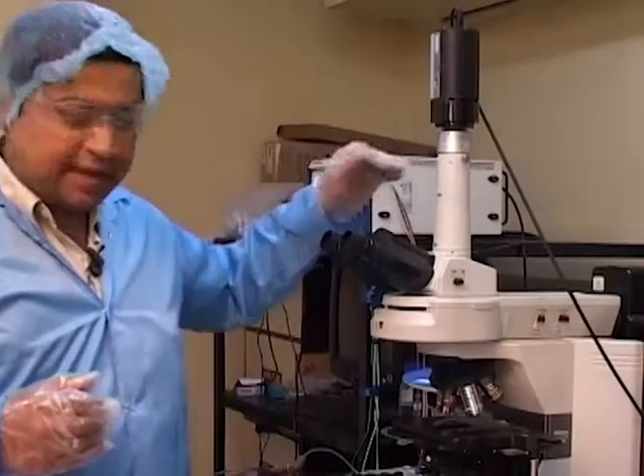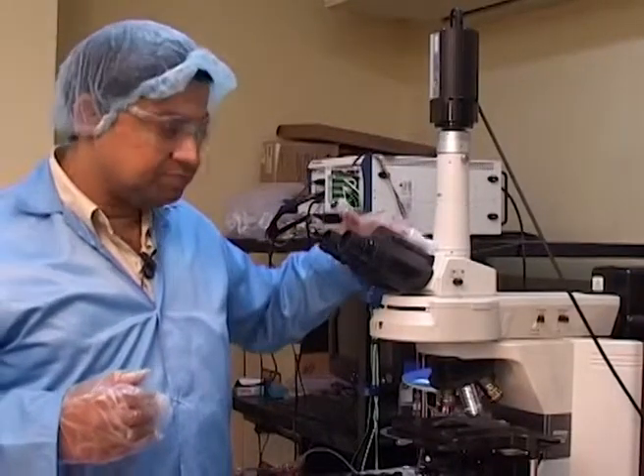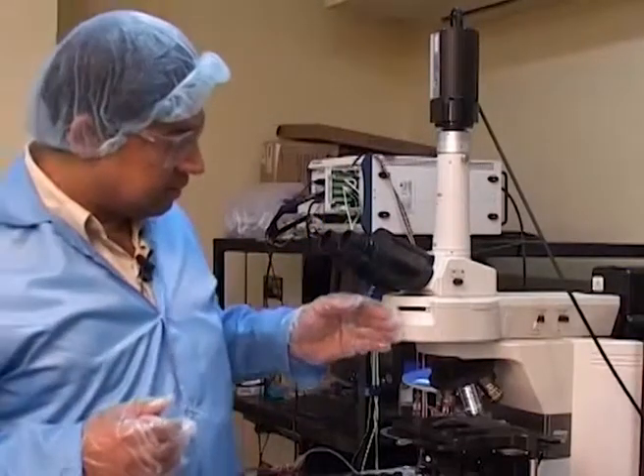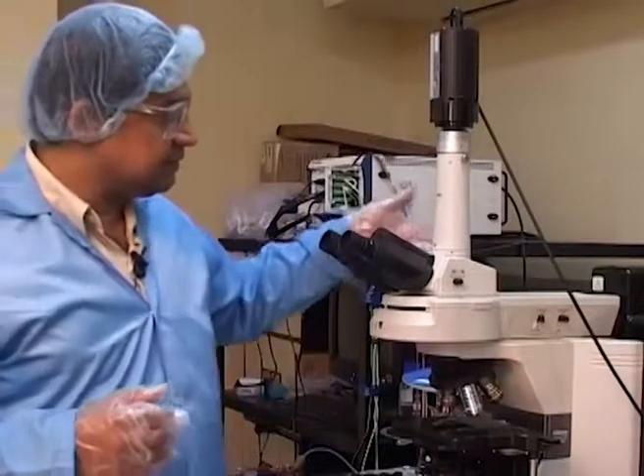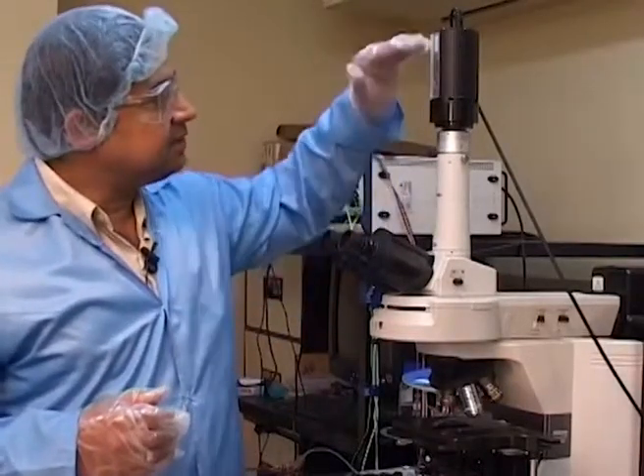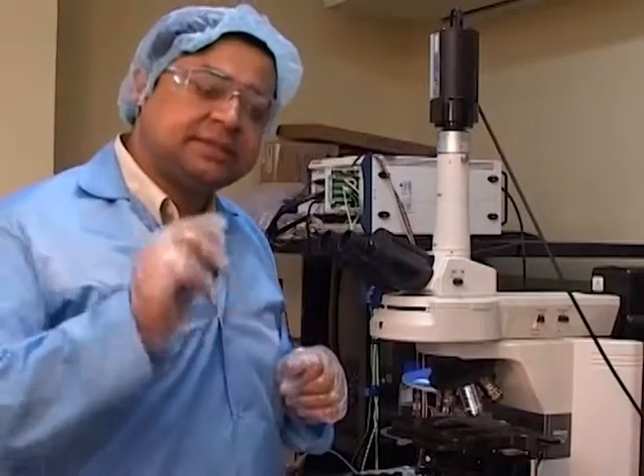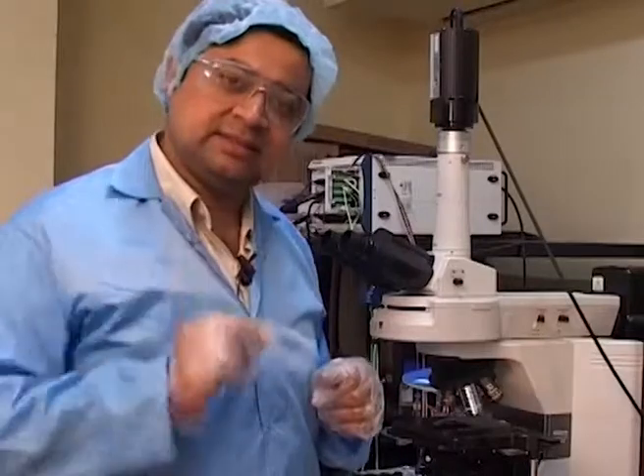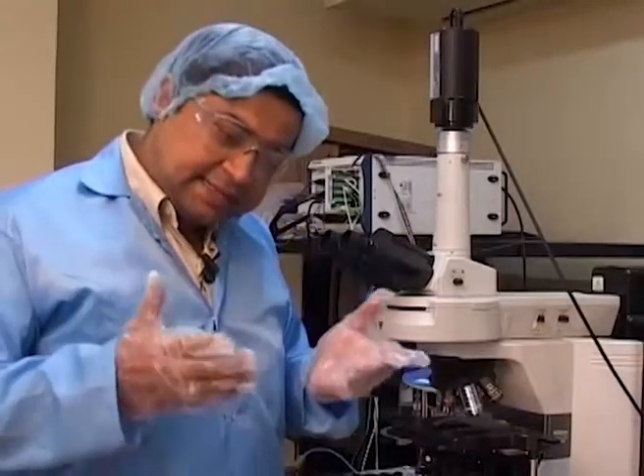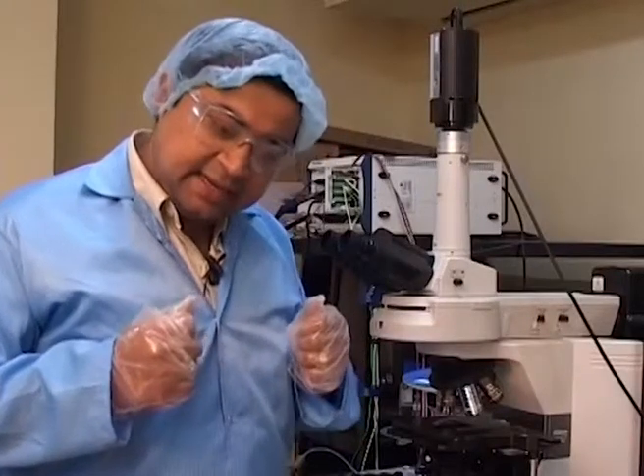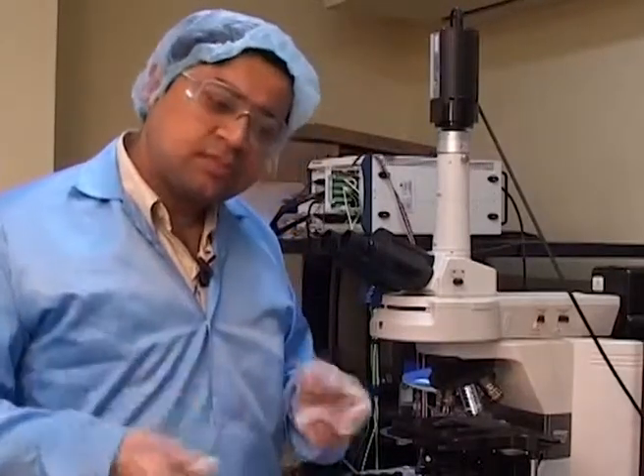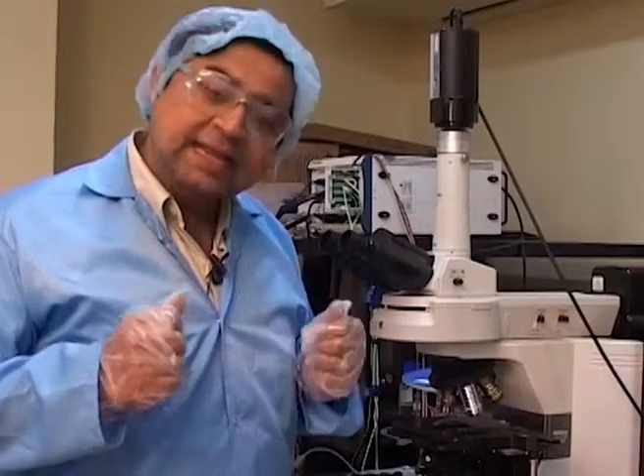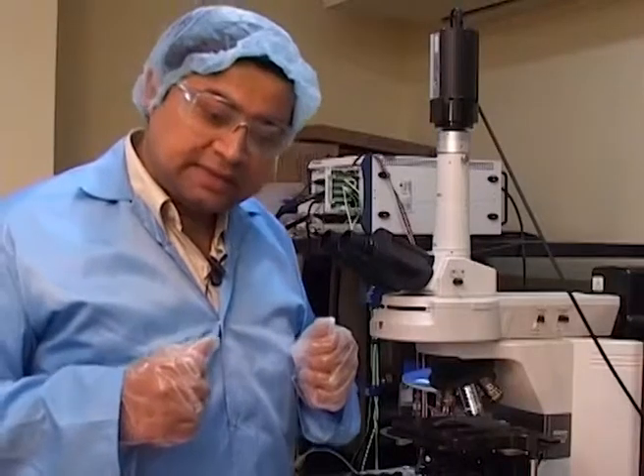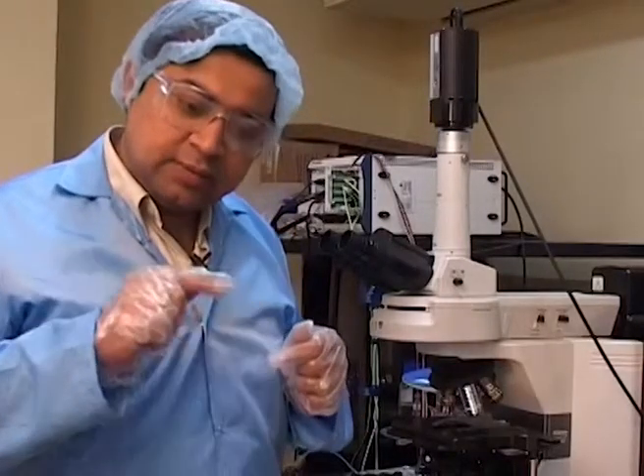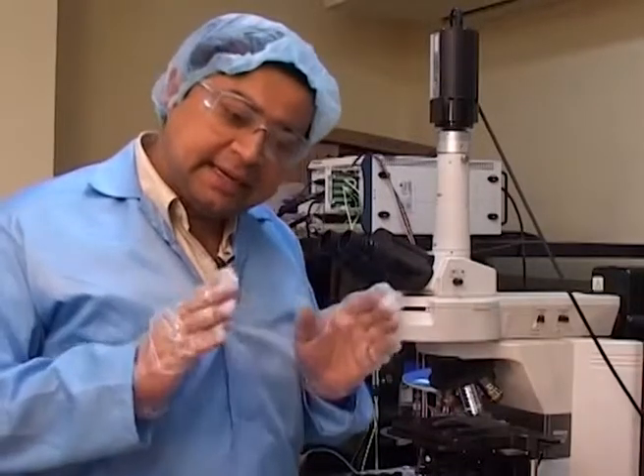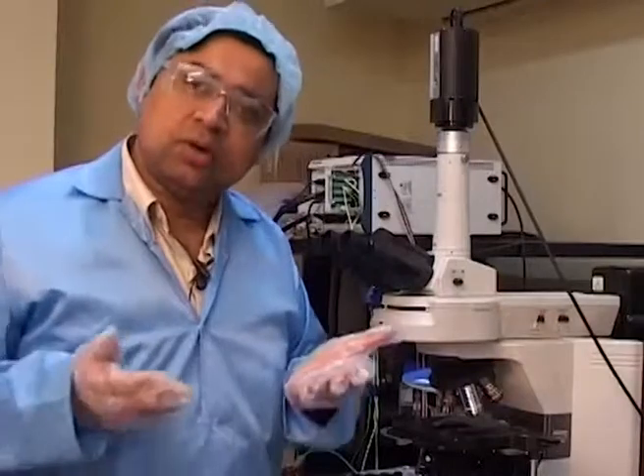So, essentially, whatever light intensity is allowed past the dichroics and the filters actually goes past this tube here, and there is a small Peltier cooled CCD chip which has thousands or millions of these pixels, which are independent devices. So, the idea is, as the intensity of the light falls on these devices, there is a transduction process, there is a generation of electrons from the photon, and that gives you a signal. Okay, that gives you an aspect about what is the intensity, what are the different textural profiles from which the light has been reflected, and that can be reconstructed simply to make what you call the real image.